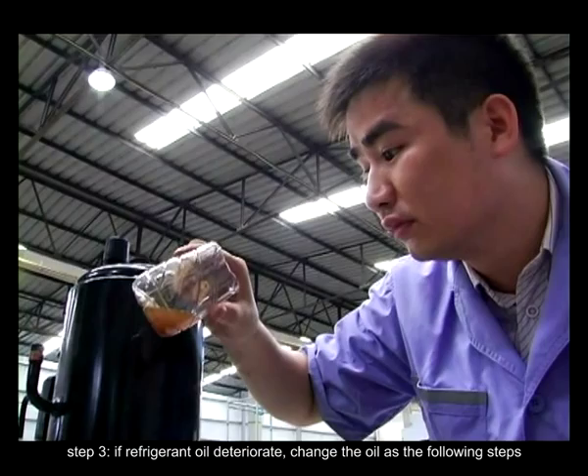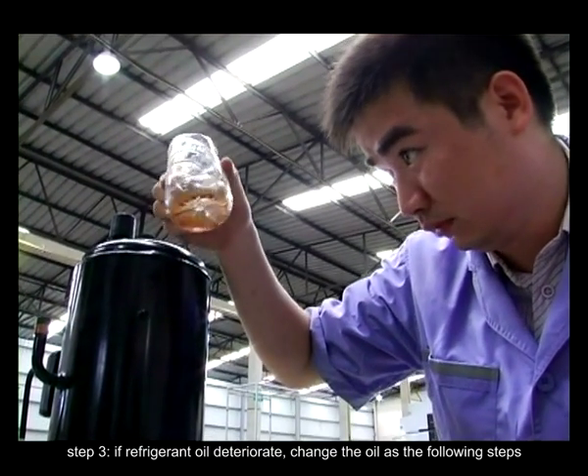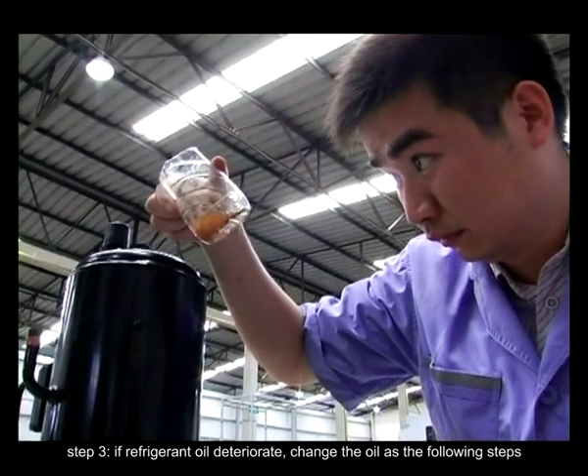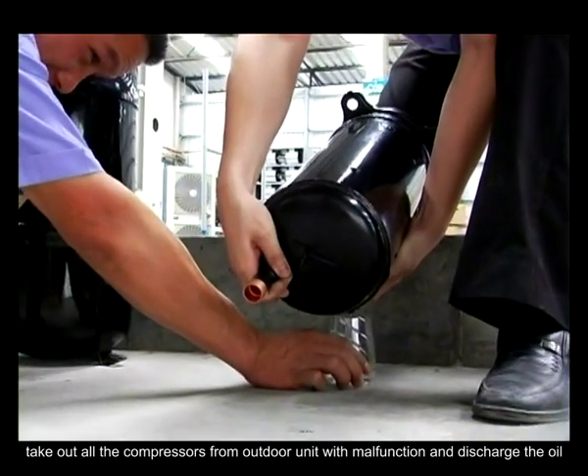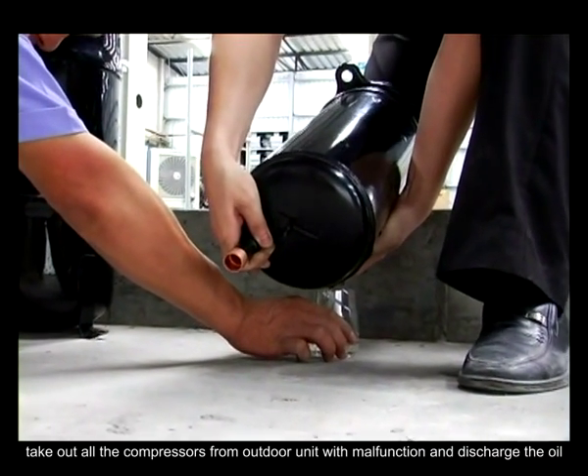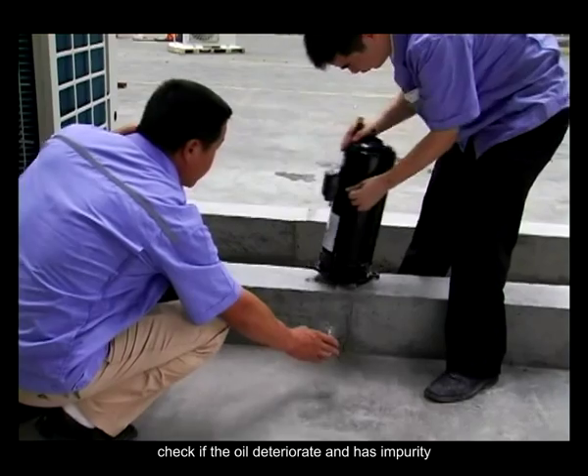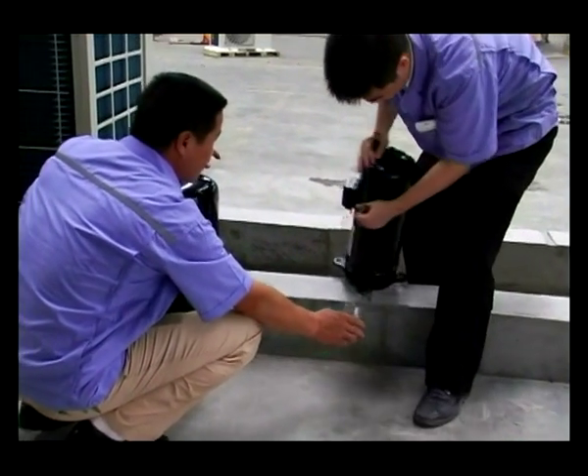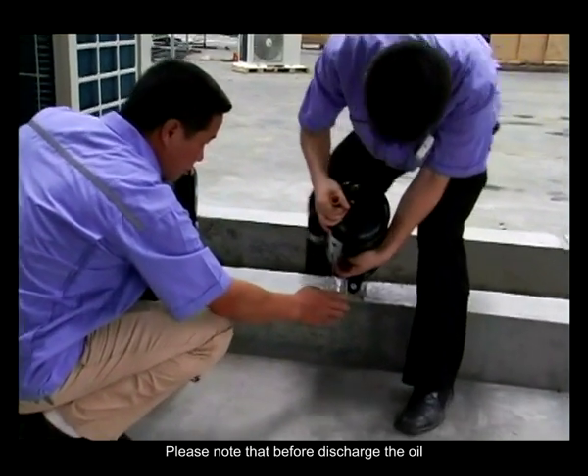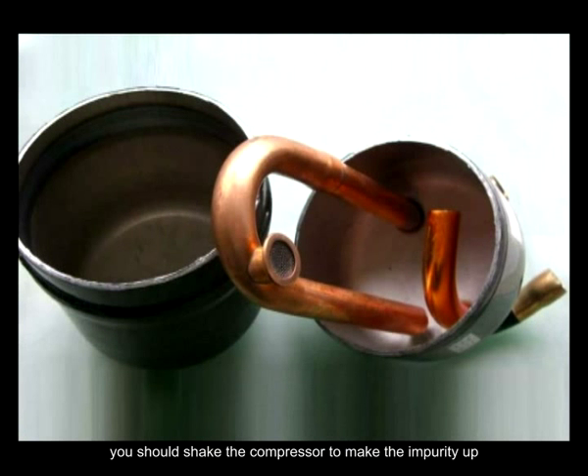Step 3. If the refrigerant oil has deteriorated, change the oil as in the following steps. Take out all the malfunctioning compressors from the outdoor unit and discharge the oil. Check if the deteriorated oil has impurity. Please note that before discharging the oil, you should shake the compressor to bring the impurity up.